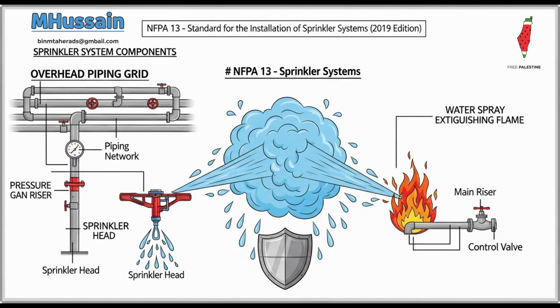Okay, so if the obstruction is 4 feet away, the water spray needs a full 12 inches of clearance just to successfully pass over it and develop its pattern without creating a shadow underneath. Exactly. And the closer the obstruction gets, the tighter that rule becomes. If the obstruction is closer than 1 foot, 300 millimeters horizontally, the deflector must actually be positioned at or below the bottom of the obstruction. Literally 0 distance above is allowed. This level of precision is all designed to eliminate those water throw shadows. Because during a fire, those shadows become unprotected areas where the fire can just reignite or grow completely unchecked.